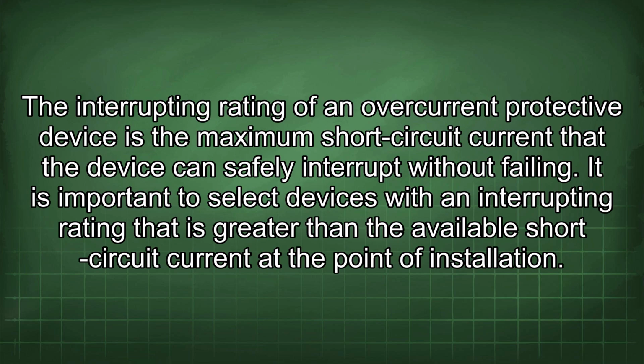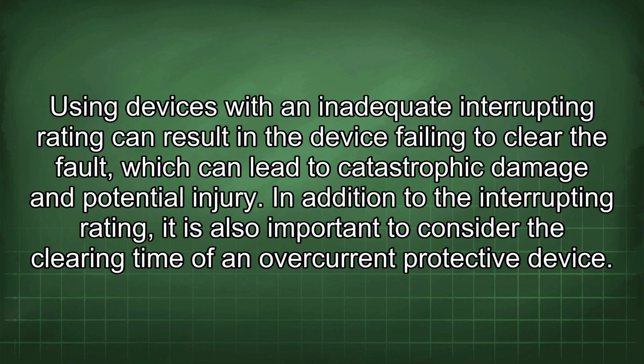The interrupting rating of an overcurrent protective device is the maximum short-circuit current that the device can safely interrupt without failing. It is important to select devices with an interrupting rating that is greater than the available short-circuit current at the point of installation. Using devices with an inadequate interrupting rating can result in the device failing to clear the fault, which can lead to catastrophic damage and potential injury.